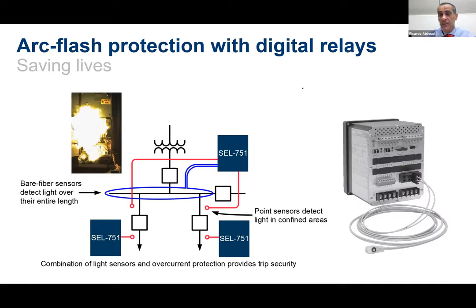How fast can this relay trip? Two milliseconds. We have high speed output contacts, the light sensor is really fast, and we have a special overcurrent function that is really fast also. So this relay can detect an arc flash and send the trip to the breaker in only two milliseconds. This is saving lives in different parts of the world. It is a really good approach for medium voltage switchgears, and it can be applied to low voltage and medium voltage switchgears. And what is the price that we put on a life? The thing here is not how expensive this is, it's the benefit of saving lives.